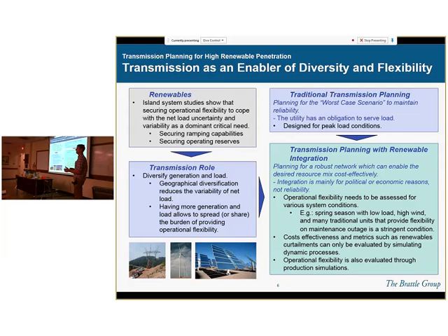And so we can see what happens if we have a ton of renewables, what the impacts of things like flexibility are, and also the impacts of different types of operating reserves, and how we determine the amount and type of operating reserves that we keep. From those studies, we see that these are critically important aspects of integrating renewables. You really can't do it without them unless you're going to curtail most of the renewables that you're generating.